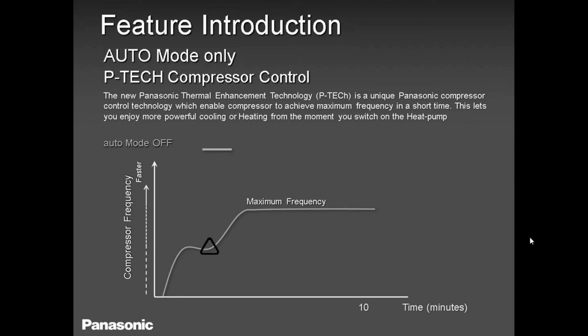Then we have this compressor of ours, very smooth, very quiet. Basically, when you turn it on for the first time, the compressor will run for less than 3 minutes at a very low frequency, and after 3 minutes it's going to pick up its frequency to the maximum, at least for the first 10 minutes, to give you enough heat or cooling to keep you going. Then after 10 minutes, the compressor is going to start slowing down and maintain a comfort zone. If you compare to our competitors, we have a very positive and better response speed from our compressors, all models across.